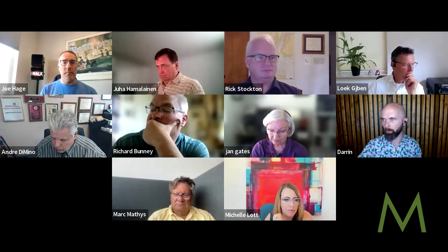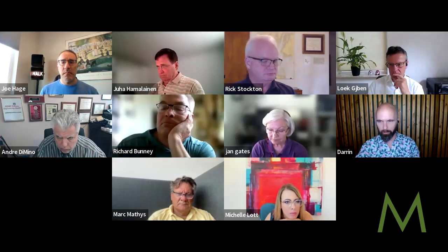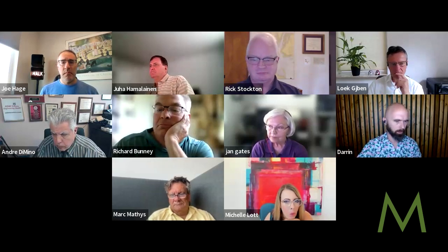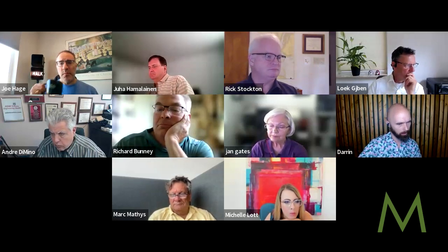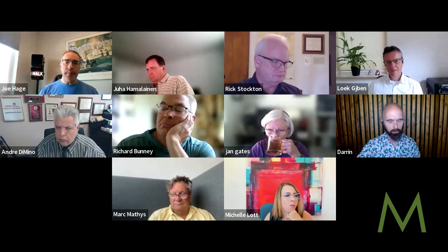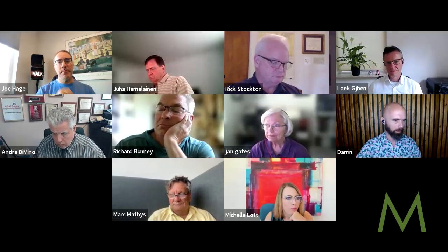Second, after the US, the EU does have their own list. Again, I think the link is in the chat here. I believe that's probably for the MDR consensus standards, which is much smaller than the list out of the US. Currently, I believe I counted 26 under MDR, and before that 268 under MDD.